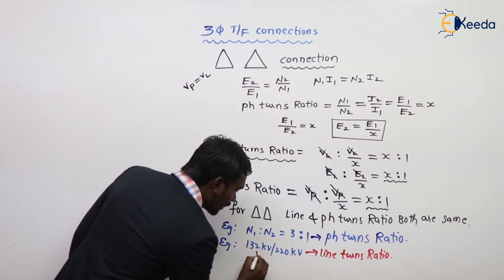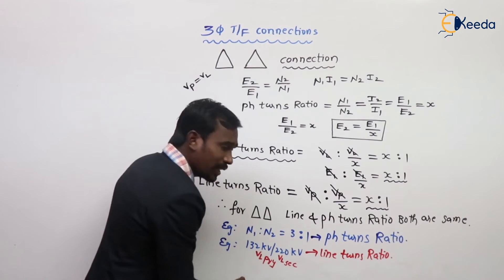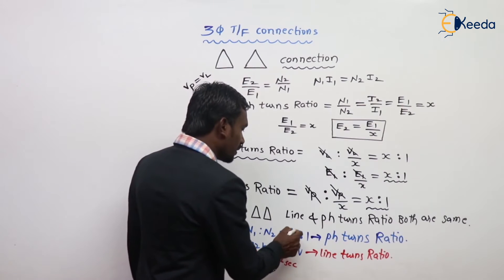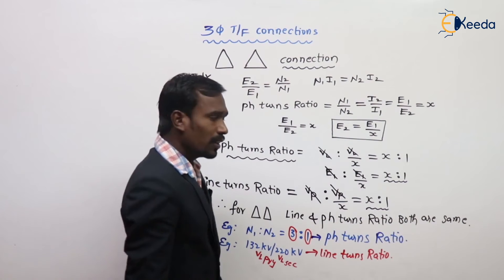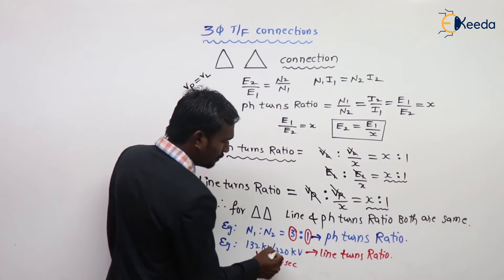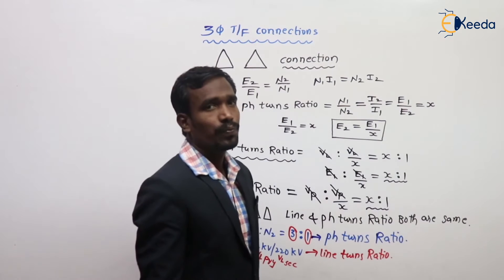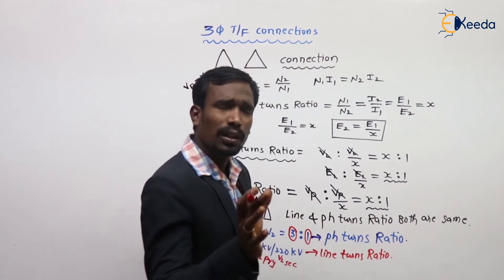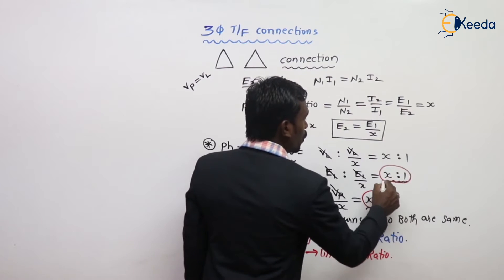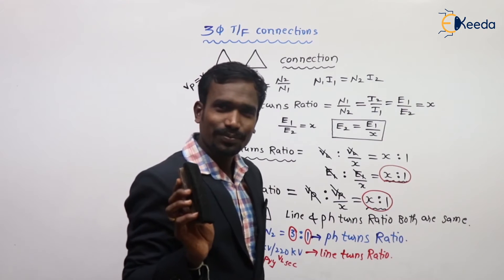When voltages like 132 kV / 220 kV are given, that represents the line voltage of primary and line voltage of secondary — the line turns ratio. When N1 to N2 is given, that is the phase turns ratio. This is just an introduction about line turns ratio and phase turns ratio. For delta-delta, both are the same.